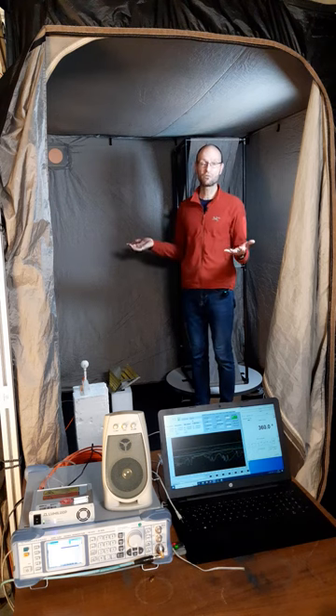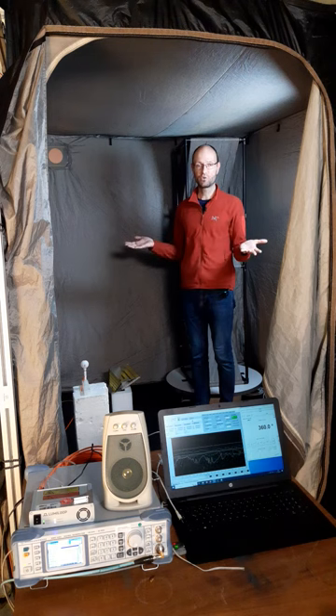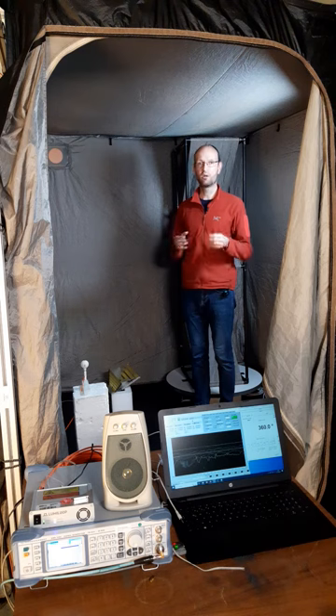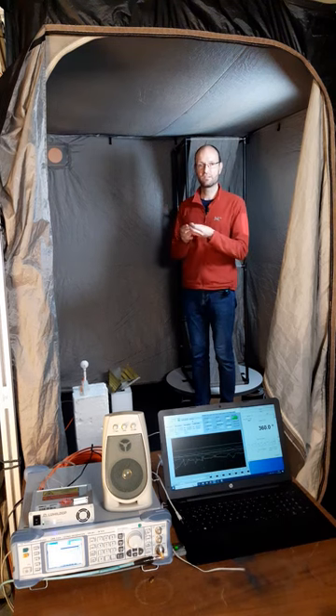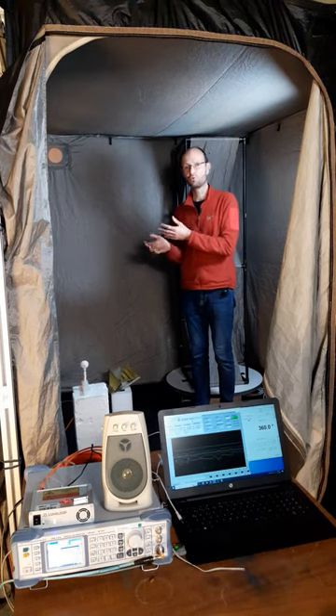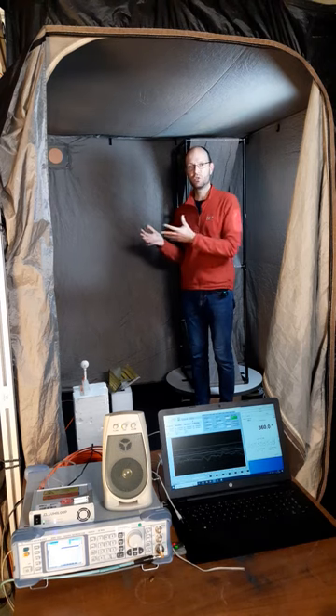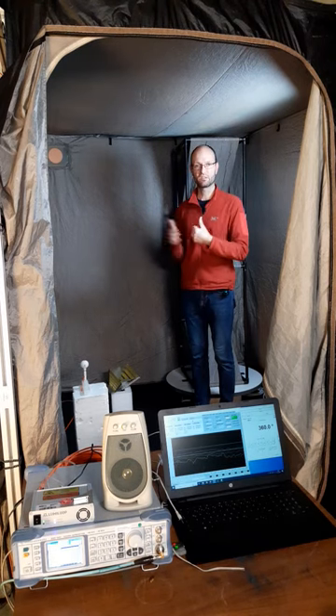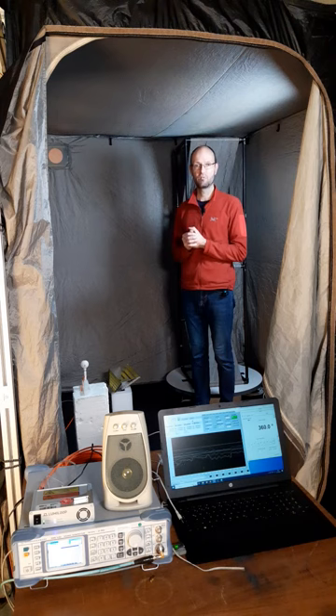And the disadvantage, of course, is that in such a reverb chamber, you get no information about direction. You don't know in which direction you have the highest emission of your device under test, and you don't know from which direction your device is most susceptible in some immunity test.